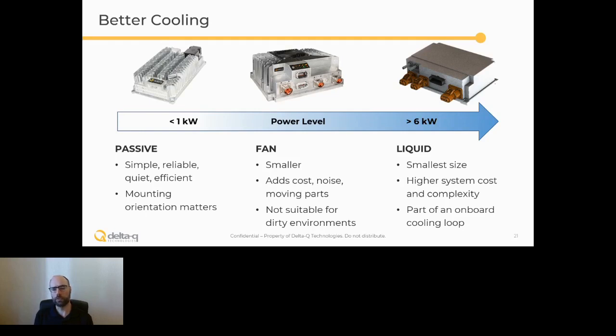Somewhere around 6 kilowatts is the break point where liquid cooling tends to make more sense, although this is more application specific. Liquid cooling gives you the smallest size for the converter, but not necessarily the smallest size for the system, because you have external components like the pump, radiator, coolant reservoir, hoses, etc. So liquid cooling tends to make sense when you're installed on a vehicle that already has a liquid cooling system for the traction system or to cool the battery, where you're part of an existing onboard loop.